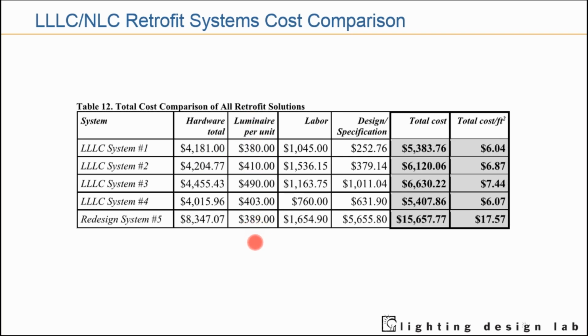If you want a per-Luminaire cost average, it's pretty similar. Another large difference is the labor to implement these systems - around $1,000 for the LLLC systems, and $1,600 for that NLC non-LLLC offering. There's a real cost differential when it came to design and specification. The way some of these zone-based NLC systems work, you have to ensure that they're designed the correct way.